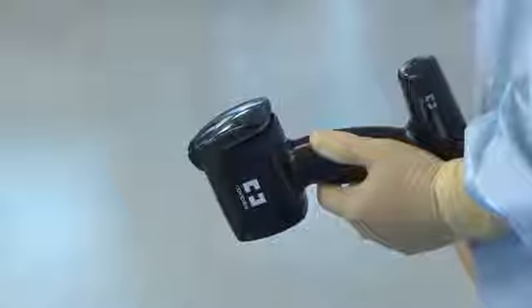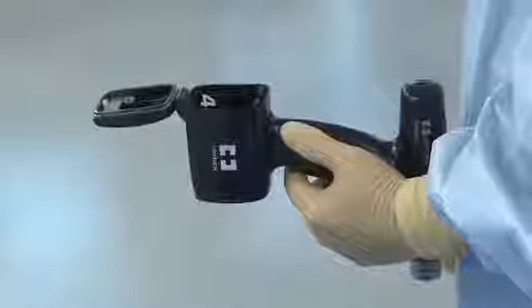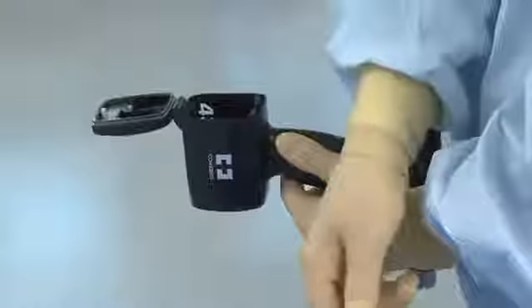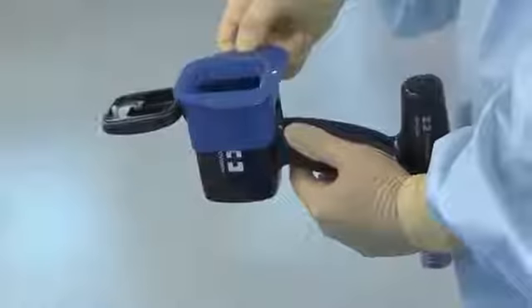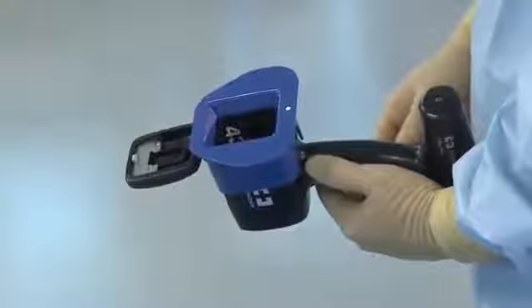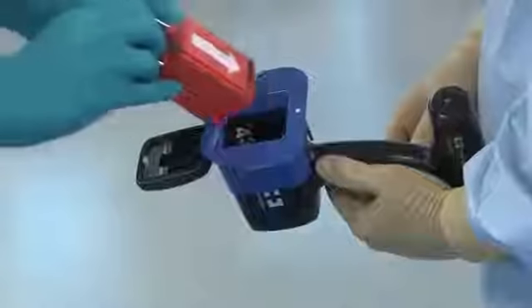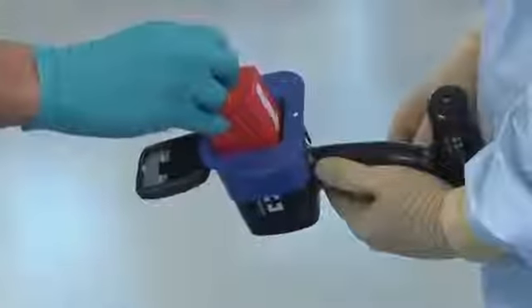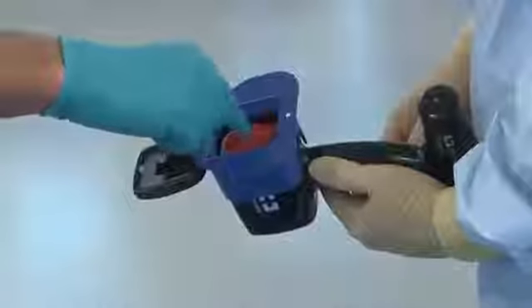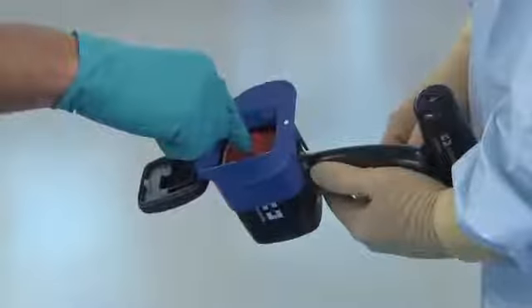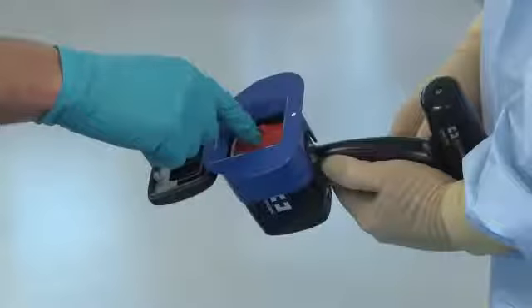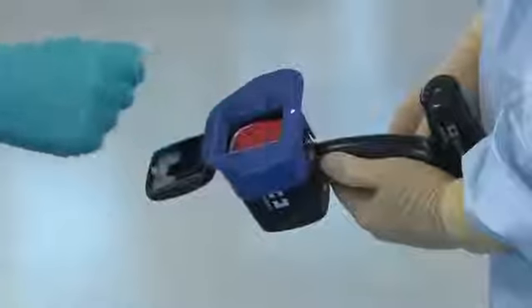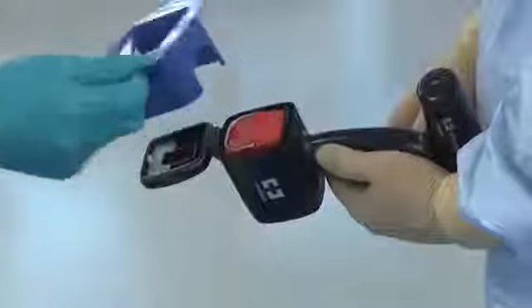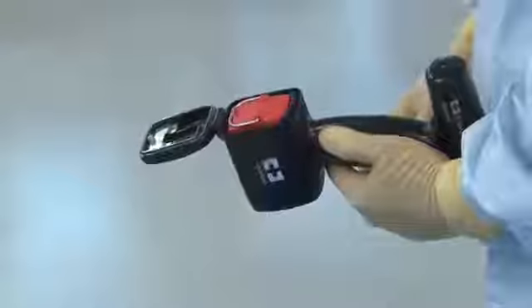The scrubbed person opens the battery compartment door fully and holds the handle so that the open battery compartment is facing up. The scrubbed person then seats the sterile battery insertion guide onto the open battery compartment. The circulating person aligns the arrow on the non-sterile battery pack with the arrow on the sterile battery insertion guide, and then inserts the battery pack through the battery insertion guide and into the battery compartment, taking care not to contaminate the handle. The circulating person ensures that the battery pack is fully seated and then removes the now contaminated battery insertion guide from the handle.